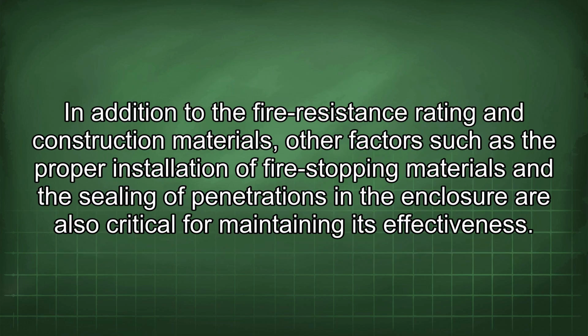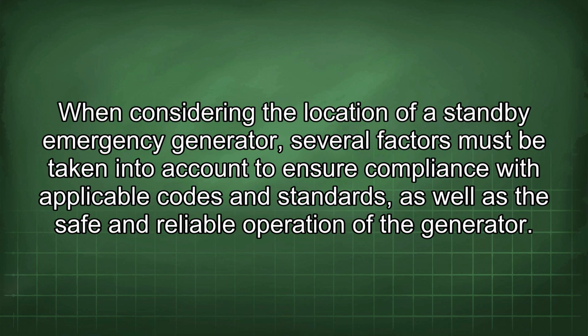In addition to the fire resistance rating and construction materials, other factors such as the proper installation of fire-stopping materials and the sealing of penetrations in the enclosure are also critical for maintaining its effectiveness. When considering the location of a standby emergency generator, several factors must be taken into account to ensure compliance with applicable codes and standards, as well as the safe and reliable operation of the generator.